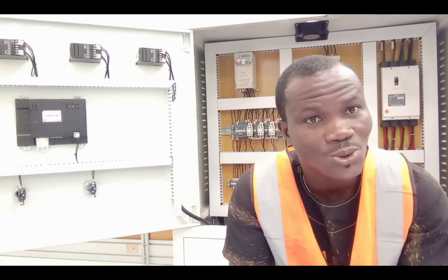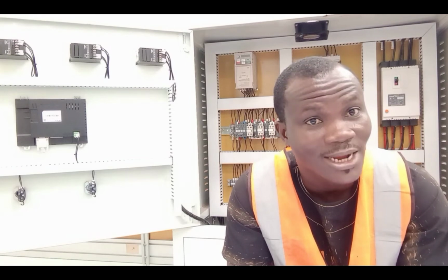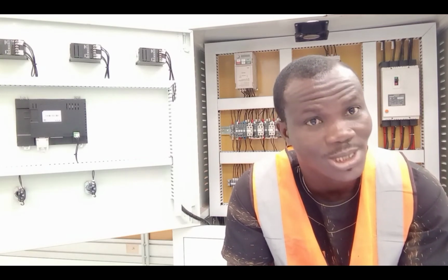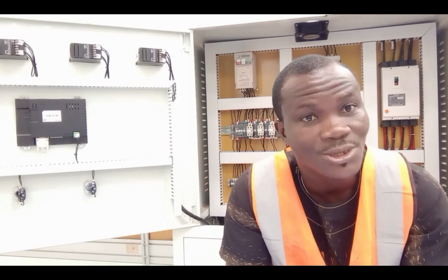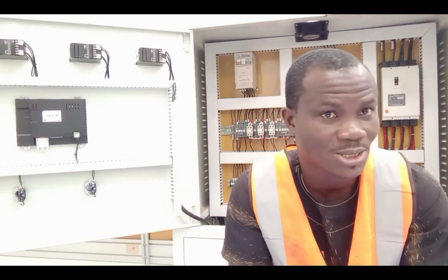So you must know the total amount of current required for the loads in that particular circuit. Secondly, you also have to have an idea of the current carrying capacity of the cables that are used in wiring that particular circuit. The third thing to do is to make a list of all the sizes of circuit breakers that can be used to protect the cables used in that particular wiring.